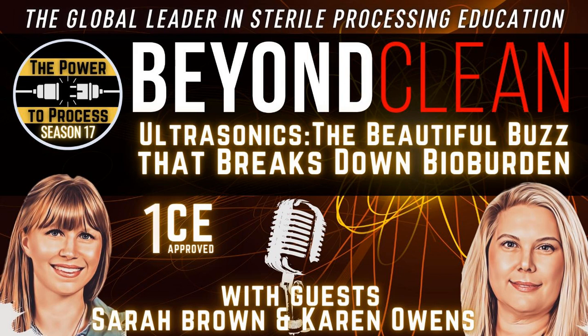You mentioned chemistries in addition to the ultrasonic energy. The chemistry piece is important as well because it's important to use a chemistry that works well with the cavitation inside the ultrasonic tank. And most instrument reprocessing instructions, or IFUs, require the use of an enzymatic cleaner. So it's really important to select an enzymatic cleaner that works well with the cavitation inside the ultrasonic tank. Specifically, there are some chemistries that have a lower foam profile that work well in that highly agitated solution. So it's important to think about not just the ultrasonic activity, but also the chemistry that gets selected with it.